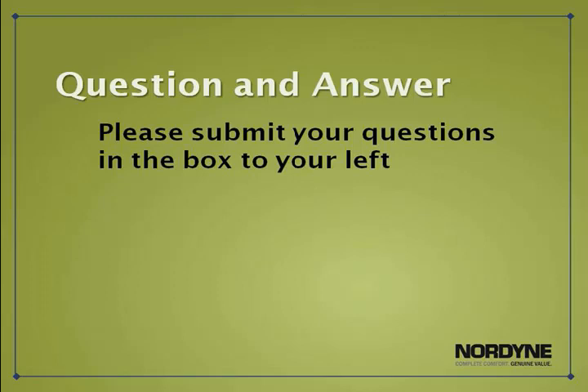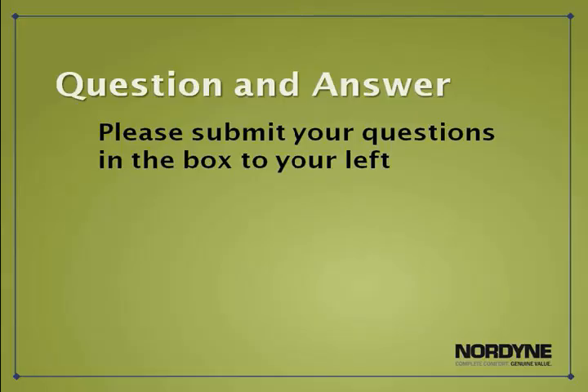Another question from Bob with MB Handy. Can I use the Broad Ocean motor tester to test the condenser fan motor? No, you cannot on this. The fault handling is handled by the interface board on the outdoor unit, and that will determine if there is a motor issue with the Broad Ocean motor on the condenser fan motor. Again, if you have any other questions, please don't hesitate to ask them.